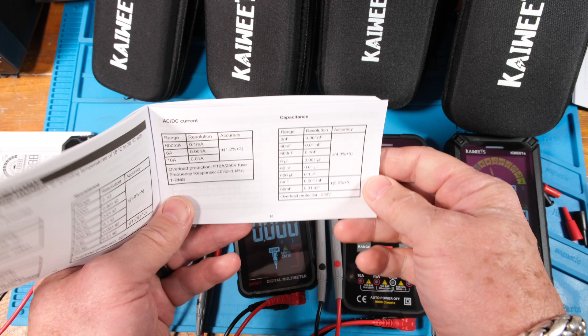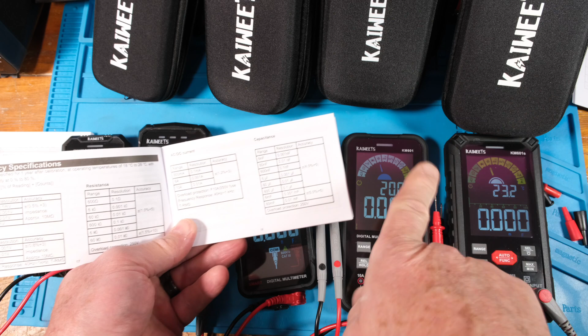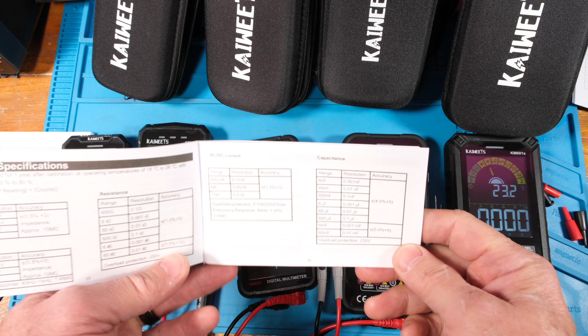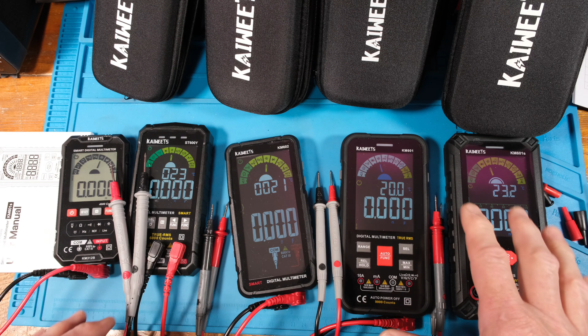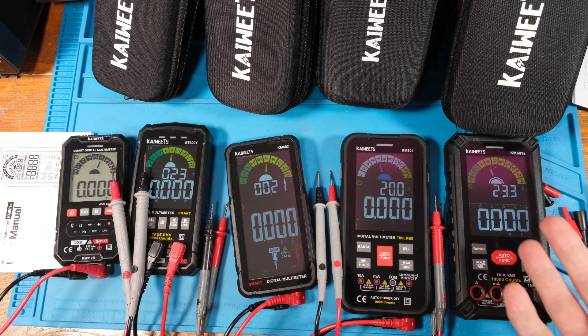Alright guys, this is kind of standard with these meters. I don't know about that one, but they're like plus minus 4%, plus 5 digits. And remember that 5 digits is that last digit. So when you have a 10,000 count, you have that one extra digit you don't have to worry about because you got extra digits, which is another plus with the high count meters. You got 3 extra decimal points, so that last one is always the least precise because it has that digit resolution plus the tolerance. So yeah, high count meters are better.